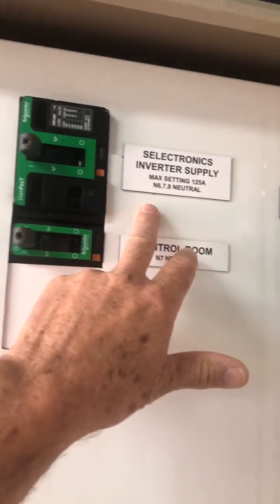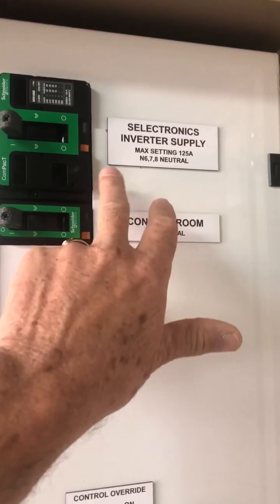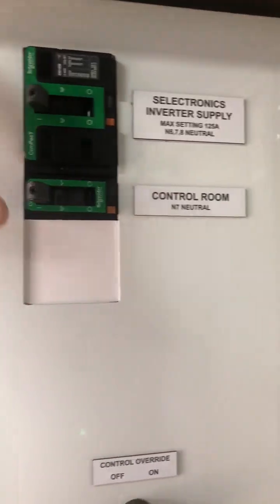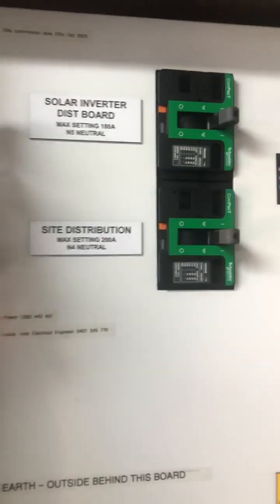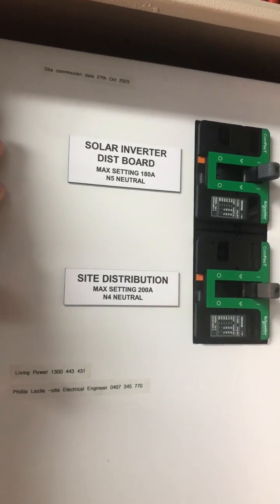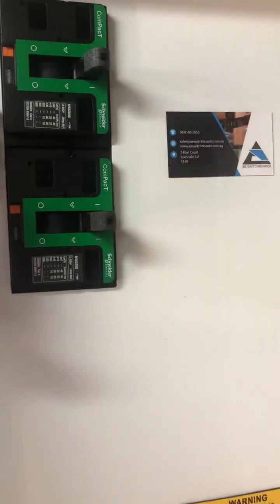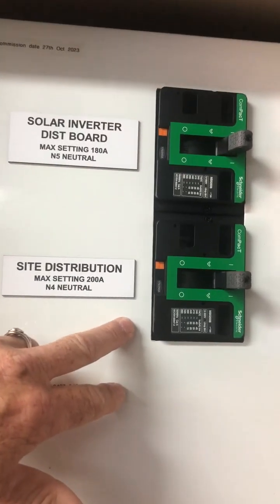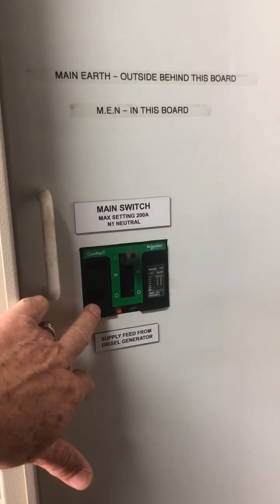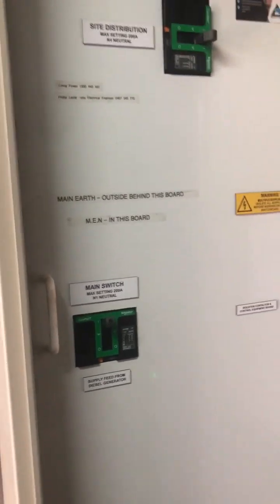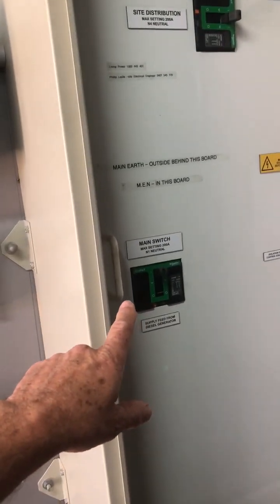So all the energy that comes from the multi-mode inverters comes into this circuit breaker here and feeds onto the bus bar. All the energy from the Fronius inverters, which are the MPPT inverters I just showed you, comes along these cables here and ends up on the bus bar through this circuit breaker, and exits this switchboard going out to site distribution. This goes out to the site. This here is the main circuit breaker that comes from the backup diesel generator. So if we need any additional support from the generator, it comes in through that circuit breaker.